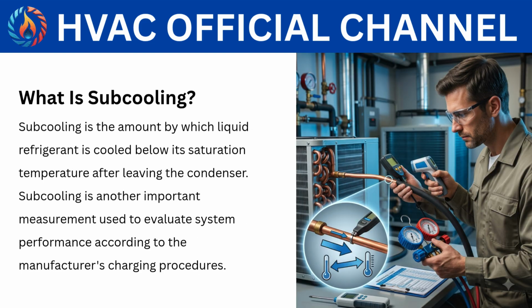What is subcooling? Subcooling is the amount by which liquid refrigerant is cooled below its saturation temperature after leaving the condenser. Subcooling is another important measurement used to evaluate system performance according to the manufacturer's charging procedures.